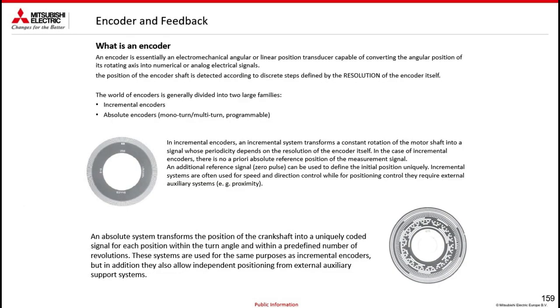We have talked about FR-A8AP, but what is an encoder? It is an angular or linear positional transducer, depending on how it is. There are two macro families, incremental or absolute, where absolute can be single rotation, multi-rotation, or programmable. Incremental encoders have n windows. In fact, the resolution is given by 360 degrees divided by n, where n represents the number of windows. And it tells me the number of impulses that arrive. This is very useful because it gives me back, for example, the motor speed.